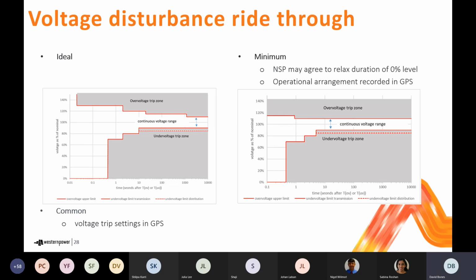The other differences that come into the minimum standard is that the network service provider may agree to additional relaxation about the duration of time at which you need to survive a zero voltage level, provided that that time duration doesn't exceed the maximum fault clearance time with no circuit breaker fail. And in addition, the minimum standard says that you need to record any operational requirements that are in place to allow the performance standard to be met. The common requirement, very similar to the one for frequency ride-through, is that any voltage trip settings need to be recorded in the generator performance standards.